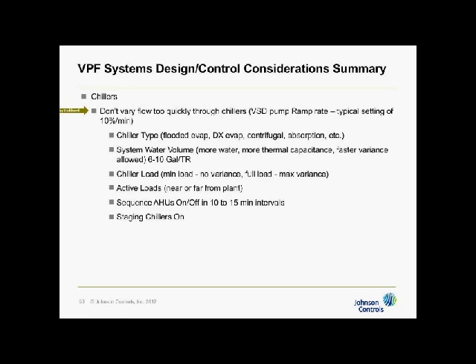If that's not fast enough, then you'll see your chilled water fluctuate. This can all be done during commissioning. Your chilled water temperature will constantly fluctuate. It can't seem to settle down. Then you need to increase that speed. So change 600 seconds to 400. That's 15% per minute. On the other hand, if it's too fast, then you've got to slow it down. Too fast is because you'll be going off on nuisance trips under low water temperature cutout.